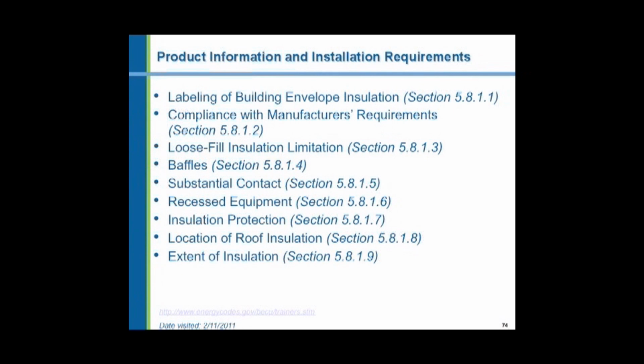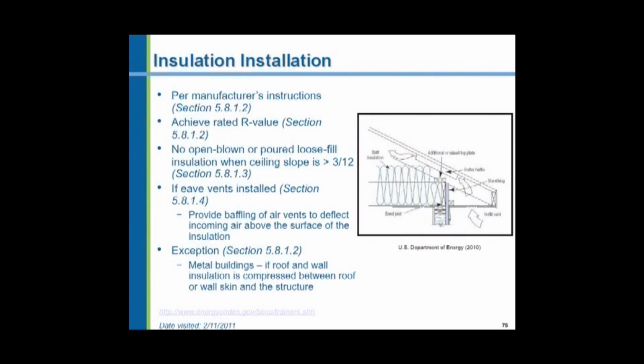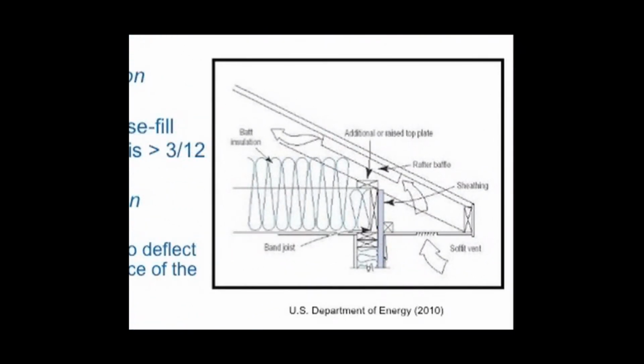That's requirements. We have to have baffles to prevent the insulation from closing up natural ventilation of the attic. We talked about substantial contact, recessed equipment. All of these things we're going to talk about here. The installation of insulation has to be limited to slopes that are less than 3 in 12. Now imagine a scissors truss where the inside slope would be not the exterior roof slope, but somewhat less. And if it's more than 3 in 12, you cannot apply a loose fill insulation simply because of the fact it's going to slide downhill. So the insulation has to be installed in such a manner as to achieve its rated R value.